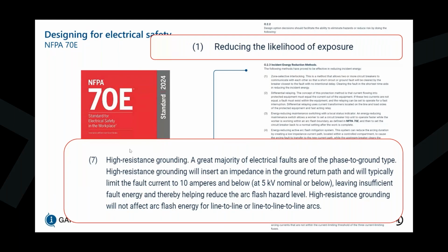The only thing with high resistance grounding is that it doesn't affect the arc flash energy for line to line or line to line to line arcs, because the NGR at the source is not going to see any of the current that's circulating between 2 or 3 faulted phases. As a result, your instantaneous function of your breaker is likely to trip in the event of a phase-to-phase or a 3-phase failure.